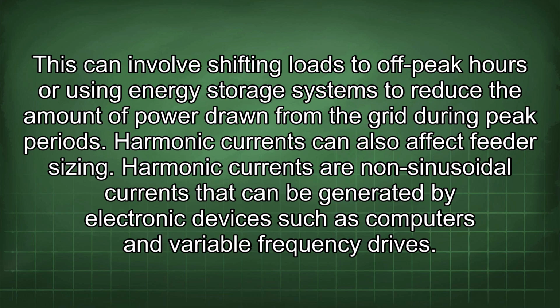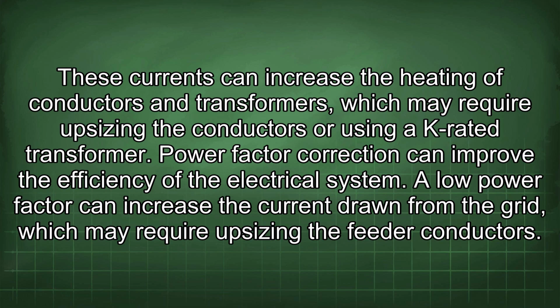Harmonic currents are non-sinusoidal currents that can be generated by electronic devices such as computers and variable frequency drives. These currents can increase the heating of conductors and transformers, which may require upsizing the conductors or using a K-rated transformer.